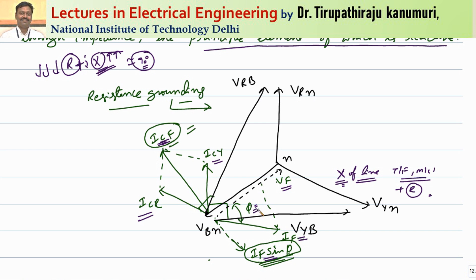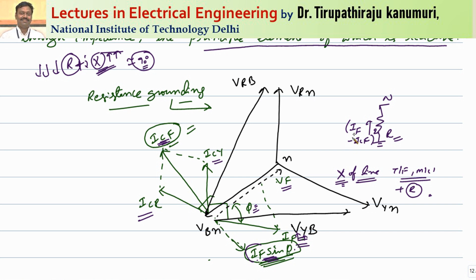Since phi is less than 90 degrees, in order to get the required value of IF sin phi, the fault current IF required will be very high. This fault current returns through the fault resistance or ground resistance, passing a current equal to IF minus ICF. Due to this, I-squared times the neutral resistance produces heat — a continuous power loss. The disadvantage of resistance grounding is this huge power loss whenever fault current passes.